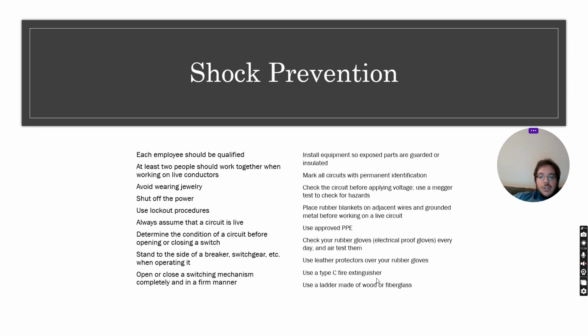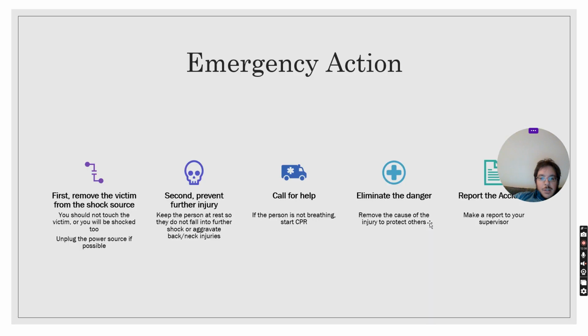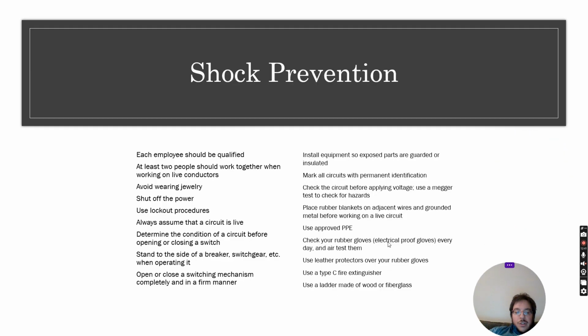You have a Type C fire extinguisher. Use a ladder made of wood or fiberglass because it's not conductive. You put rubber blankets on adjacent wires and metal when you're working on a live circuit, and that reduces the risk of electricity jumping from the wire you're working on to another close by wire. You can use a Megger meter to check for cuts to the wire or leaks in the insulation. And you can use electrical proof gloves. They're like rubber gloves, and you should wear them when you're working on a live circuit. But they do get damaged easily, so you want to test them every day to make sure that they're airtight, and then you want to use a leather protector over the rubber gloves so they don't get torn because they're very expensive and once they're torn they're ruined.